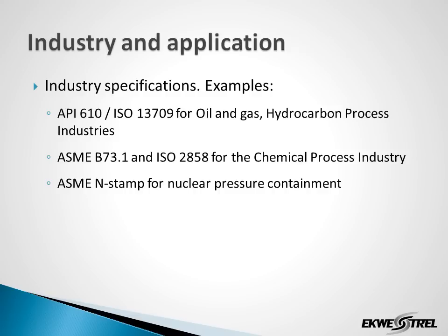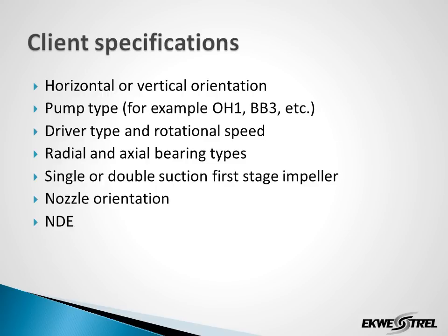Industry and application specifications play an important role. These are just a few examples of the many industry-specific types of specifications: API 610 for the hydrocarbon industries, ASME B73.1 for the chemical process industry, and so on. Client specifications also play an important role, whether the client wants a horizontal or vertical orientation, particular pump type, driver type, bearing arrangement, type of first stage impeller, nozzle orientation, and any non-destructive examination.